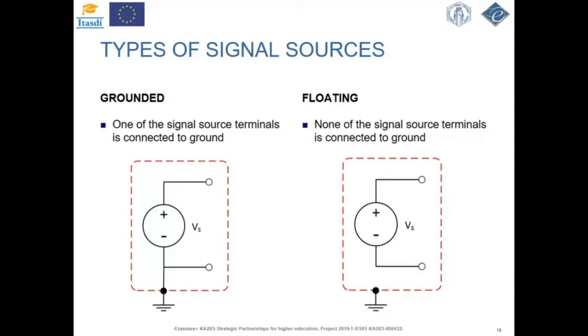Regarding the connection with the data acquisition systems, we have two types of signal sources: a grounded signal source and a floating signal source. A grounded source is one in which the voltage signals are referenced to the system ground. Having in mind that such sources use the system ground, they share a common ground with the measurement device. On the other hand, in a floating signal source, the voltage signal is not referenced to any common ground. The system ground can sometimes be wired to the source casing, if there is any, but the ground is never connected to the source leads. Some common examples of floating signal sources are batteries, thermocouples, transformers, isolation amplifiers, and so on.